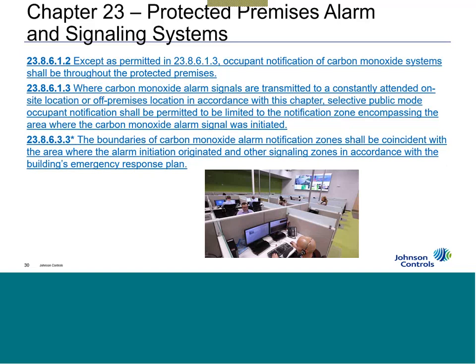So what about occupant notification? This question comes up a lot, and there's a lot of confusion out there. So let's run through this. In Chapter 23, Section 8.6.1.2, except as permitted below, and we'll get to that, occupant notification of carbon monoxide systems shall be throughout the protected premises. A lot of people stop there, and they say, okay, carbon monoxide, I need to do temporal 4 everywhere in the building. Well, let's continue on.